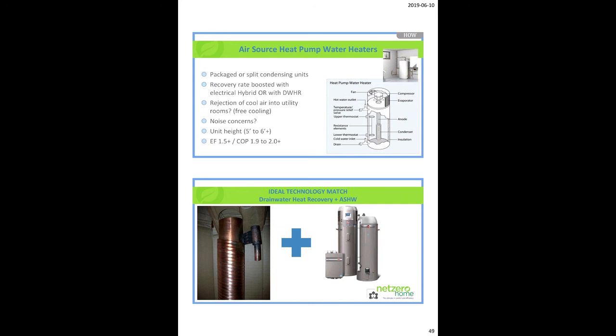Seriously. Now with units like this, the new systems - the Rheems, the Sandens, which are really efficient CO2-based systems - they now have duct kits, and this is fairly new. They didn't used to want you to put a duct with the rejected cool air coming off. They wanted it to stay in the room, and they were concerned about freezing the coils internally.